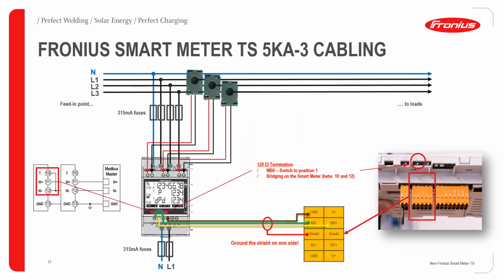And installation or cabling of the Fronius Smart Meter 5KA3, that's the commercial smart meter. Like the normal 65A3, it's also the same connection when it comes to the data cabling. Just the data plus and data minus in the Snap inverters are called M0 plus and M0 minus in the Gen 24. So you will be using M0 plus, M0 minus, and the ground. And please ground the shield of the cable on one side.